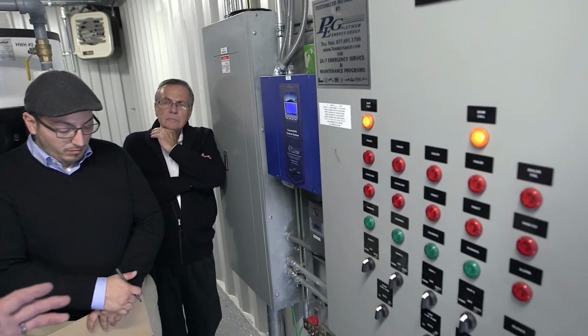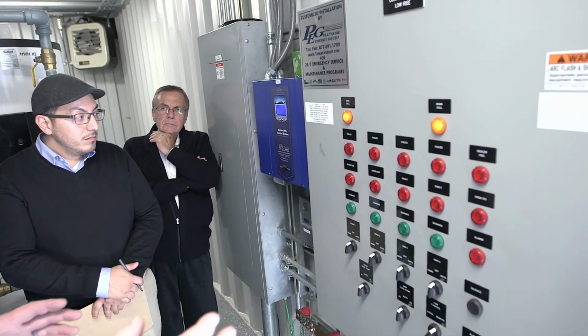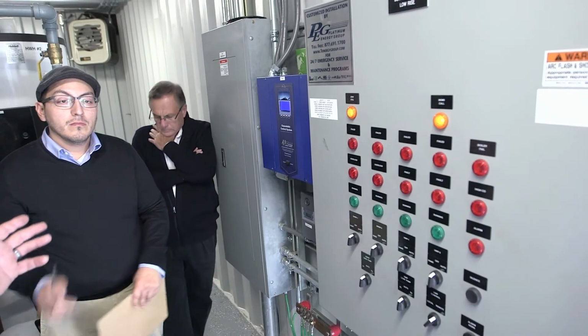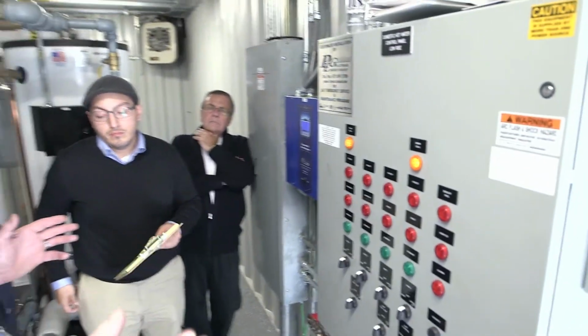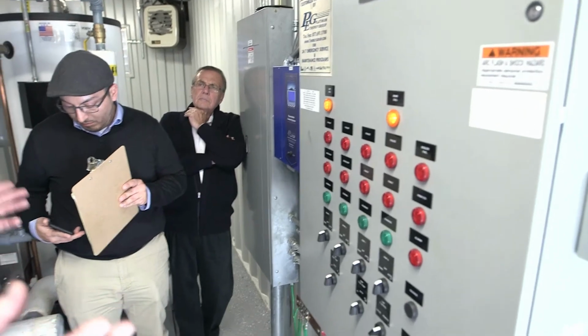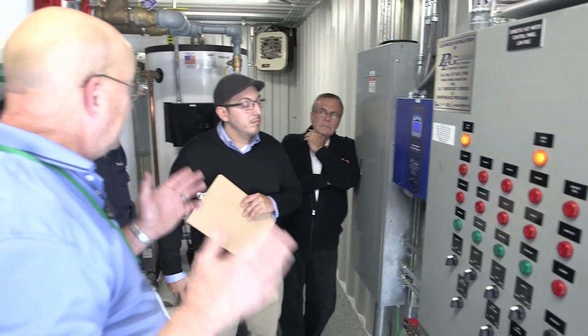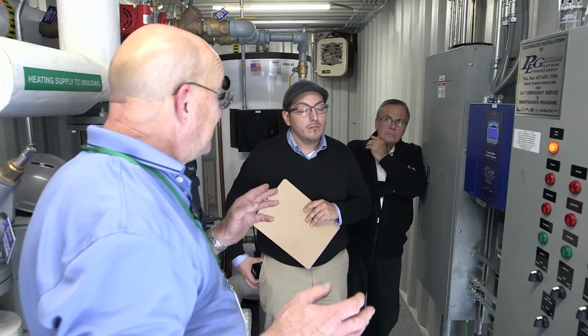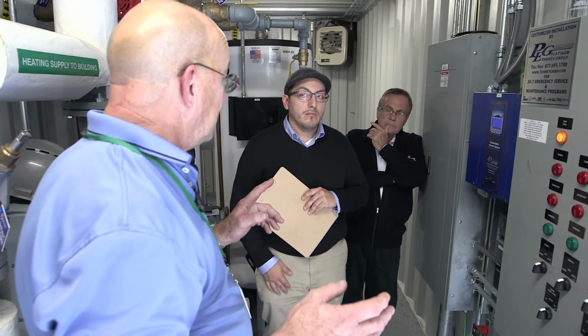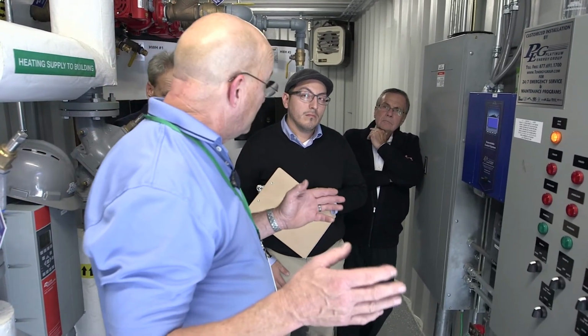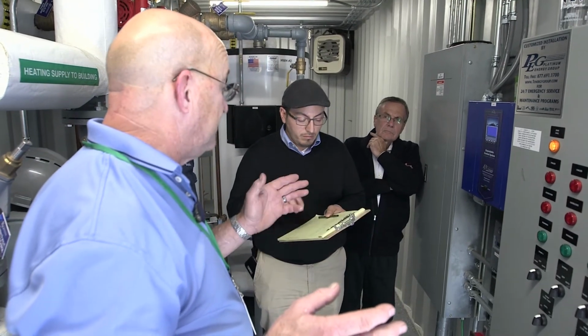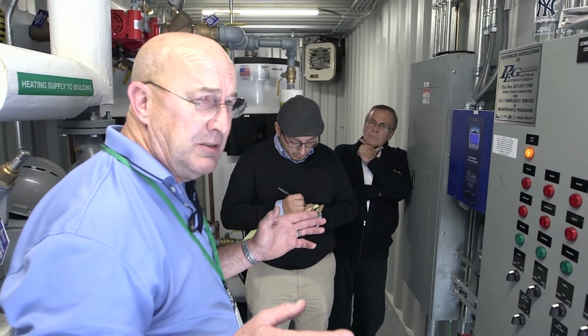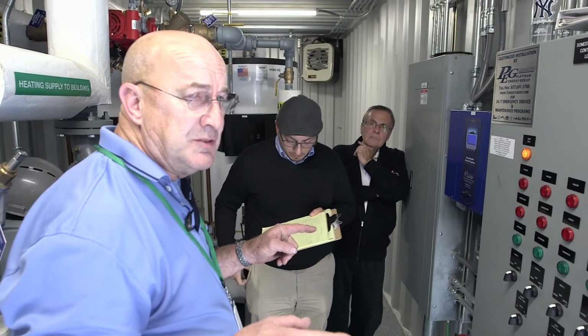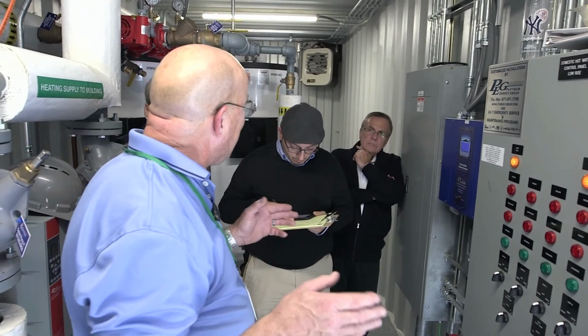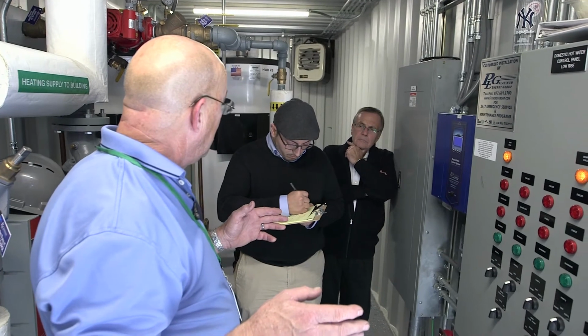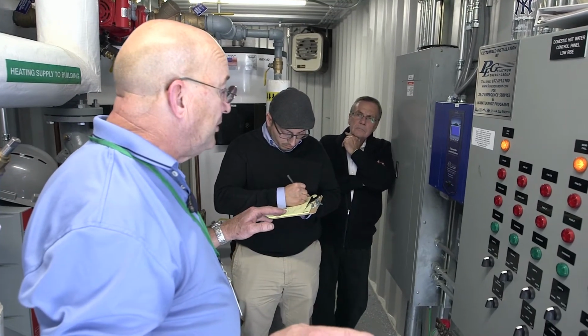It takes the outdoor temperature. It says, like today, it's above 55 degrees, I don't need to run today for heat. It will not let the boiler run. Unless, by the new law, an average of several of the apartments. How many sensors here? 28? The repeaters or the sensors? 53 sensors. So it's going to take an average of 10 sensors, and it's going to say, how are we doing?